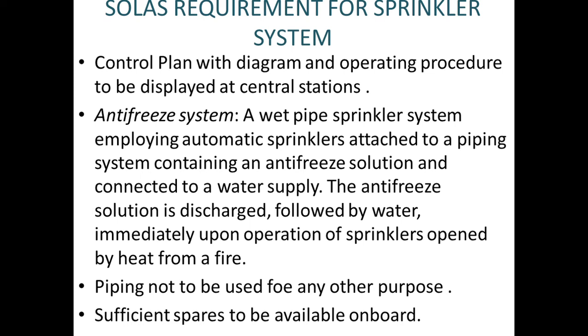It's self-explanatory. Now, this is an antifreeze system, a wet pipe sprinkler system, because in wet pipe there are chances that the water will freeze. It employs automatic sprinklers attached to a piping system containing an antifreeze solution, so that a ship sailing in areas where the temperature is quite low, where water freezes, is protected. It is connected with the water supply. The antifreeze solution is discharged, followed by water, immediately upon operation of a sprinkler opened by heat from a fire. So this is the antifreeze system that is also installed.